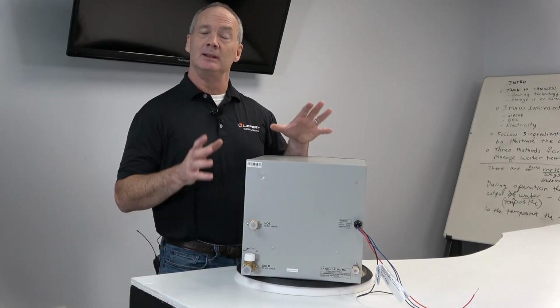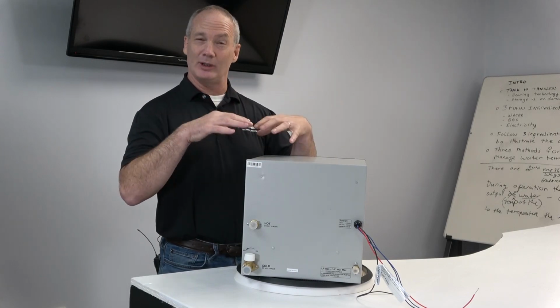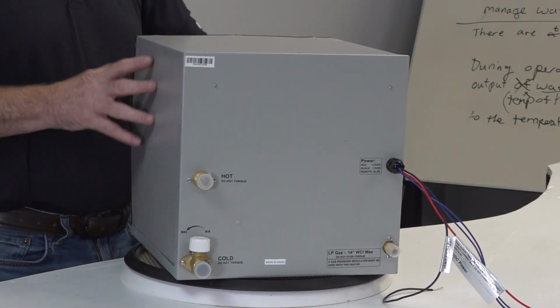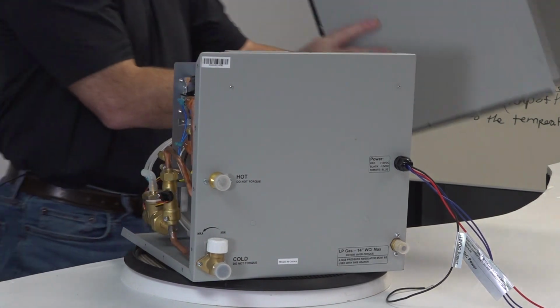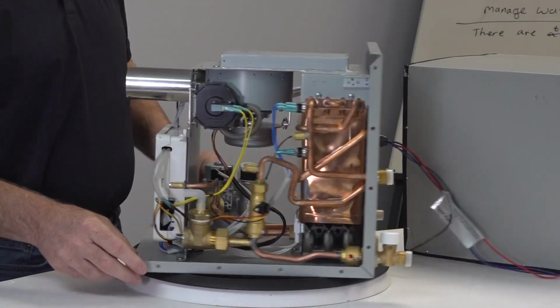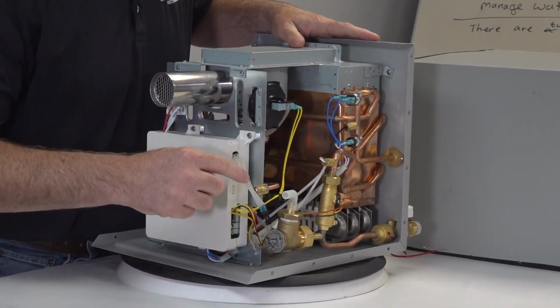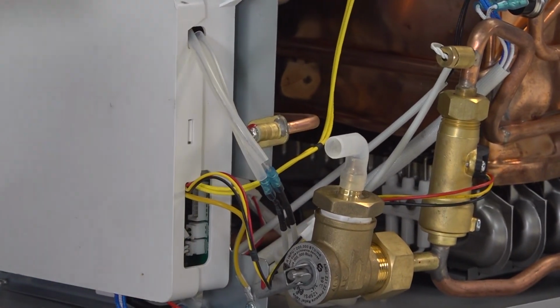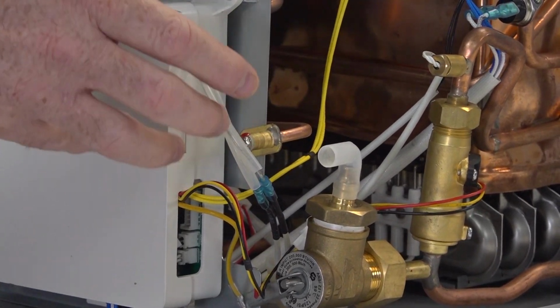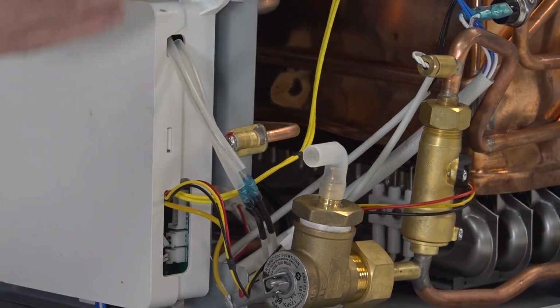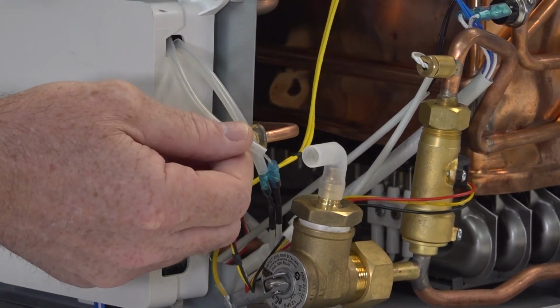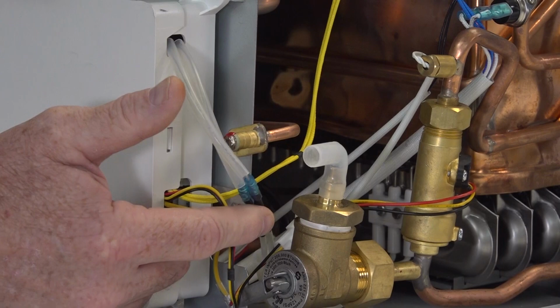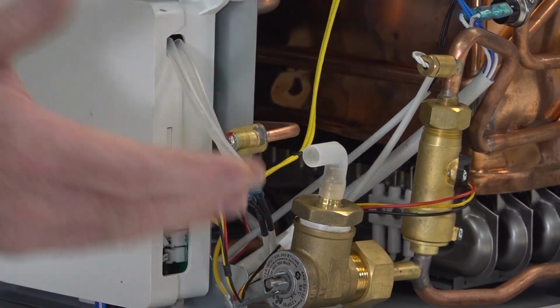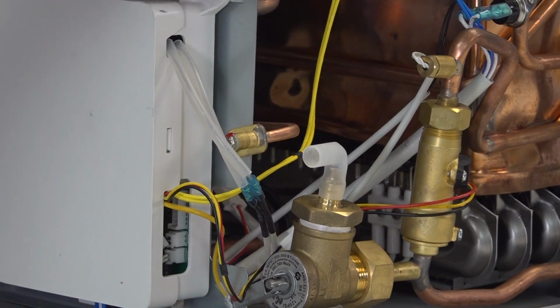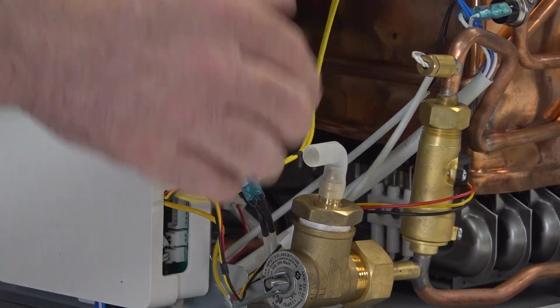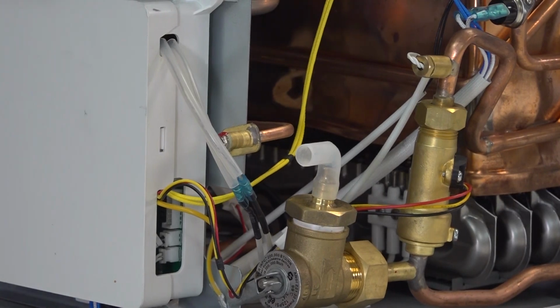For this next inspection, let's remove the cover so you can take a look inside the appliance. Take a look at these highly insulated wires. This is for your ignition, and it takes high voltage to run the igniter, so that's why you have that extra insulation on there. So you're making sure that these wires are not open for sure and shorted against any of the metal, whether it be the firewall or anywhere back all the way to the igniter.